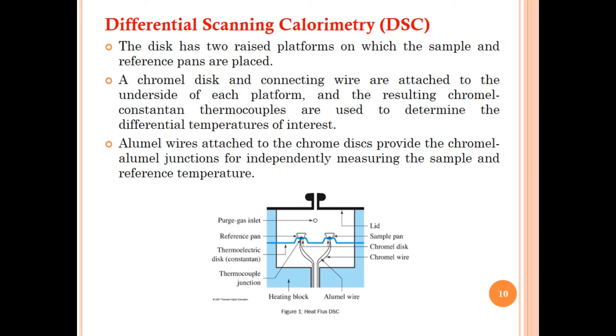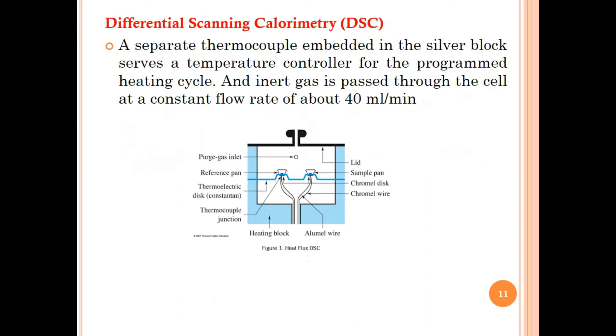A chromel disk and connecting wire attached to the underside of each platform form chromel-constantan thermocouples used to determine the differential temperature. Alumel wires attached to the chromel disk provide the chromel-alumel junction for independently measuring sample and reference temperatures. A separate thermocouple embedded in the silver block serves as a temperature controller for the programmed heating cycle, and an inert purge gas is passed through the cell at a constant flow rate of about 40 ml per minute.